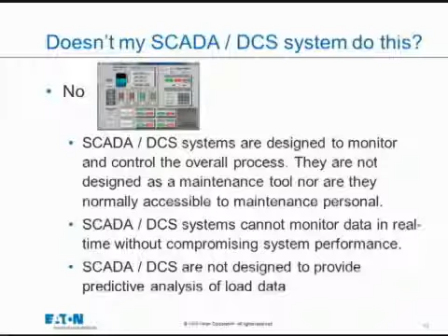So SCADA systems are never designed as a maintenance tool, nor do they have the bandwidth to be one. If it was going to do profiling and diagnostics of a load, it would have no bandwidth left for anything else, because it would be sampling every second, every half second, trying to figure out patterns. It just can't do it. It's not designed for predictive analysis, so it can't do that without jeopardizing its key function.